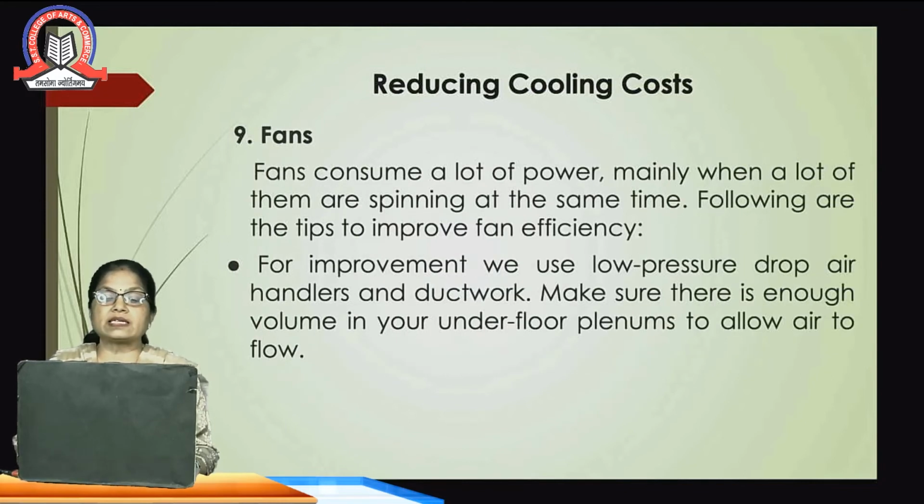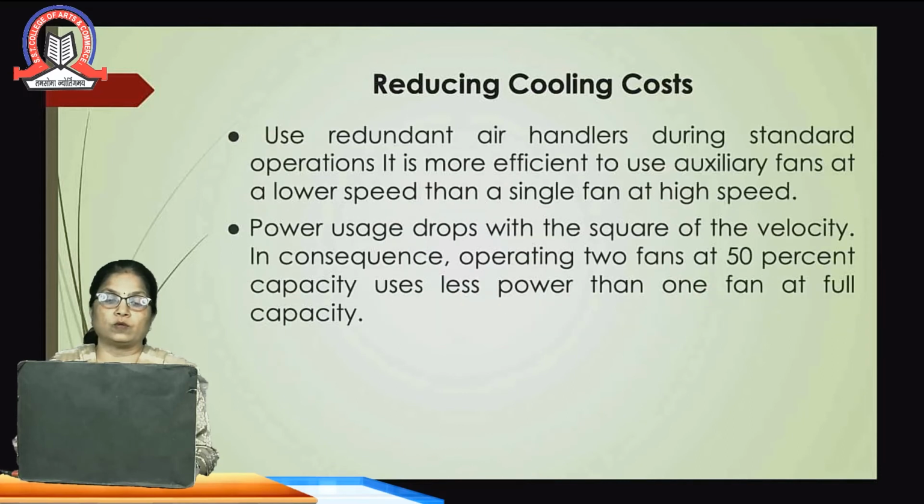Fans. Fans consume a lot of power, mainly when a lot of them are spinning at the same time. Following are the tips to improve fan efficiency. For improvement, we use low pressure drop air handlers or ductwork. Make sure there is enough volume in our underfloor plenums to allow air to flow. Use redundant air handlers during standard operations. It is more efficient to use auxiliary fans at a lower speed than a single fan at high speed.